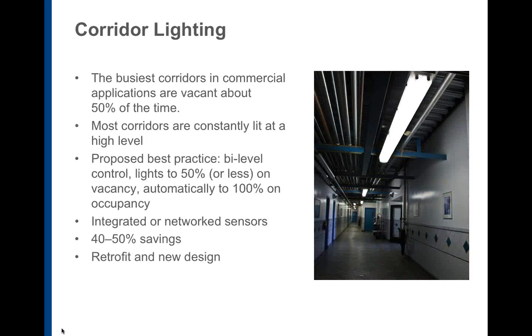The busiest corridors in commercial applications, from what we found, are vacant about half the time. That's pretty significant. We're not doing our work in the hallways. We're in our offices, classrooms, meeting rooms, conference rooms, other areas. So our proposed best practice is at least bi-level control, lights at 50% less on vacancy, automatic to 100 on occupancy, but you can also trim and set those lights at 80% maybe when it's occupied, with ample illumination for your occupants in those spaces. And this is a good strategy for both retrofit and new design. Next slide.